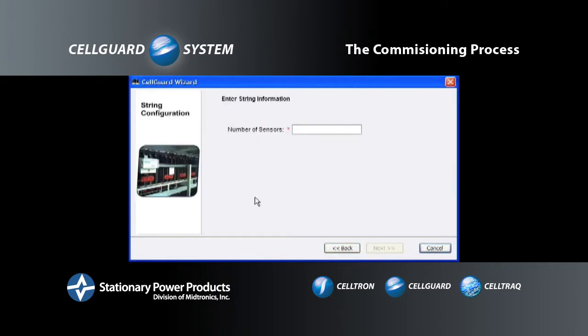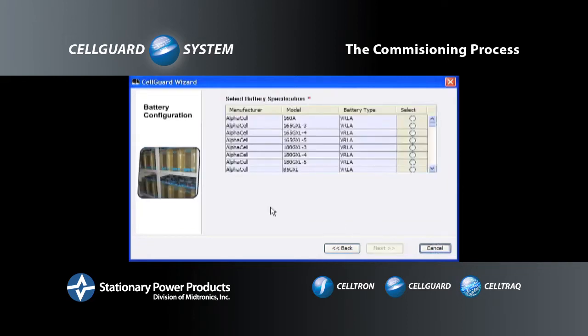Now, enter the number of sensors for the battery string you are commissioning. For our demonstration, 4 will be used. Once entered, click Next. Next, select the battery model for your installation. Scroll through the list and select the battery model being used. If your battery model is not listed, pick a model that is the same voltage and similar in amp-hour capacity for now. Later, you can change to the correct battery model in the CellTraq software.